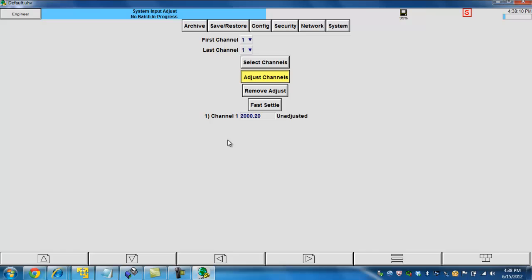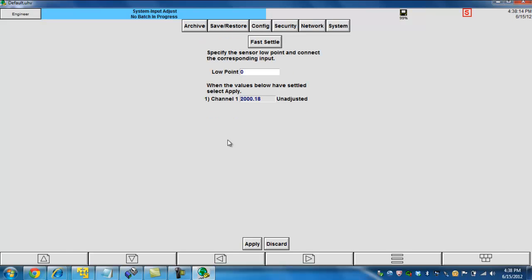When we do this, it's going to ask you for a low point value. The default is 0. You can leave it at 0, that's perfectly fine. A forced habit for me, however, is I typically will do 10% and 90% of my full scale as my low and high point. So based on a scale of 0 to 2,000, 10% of that would obviously be a low point of 200.